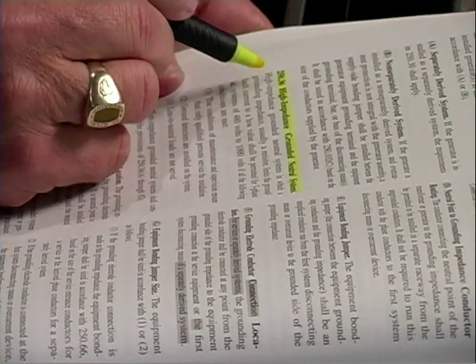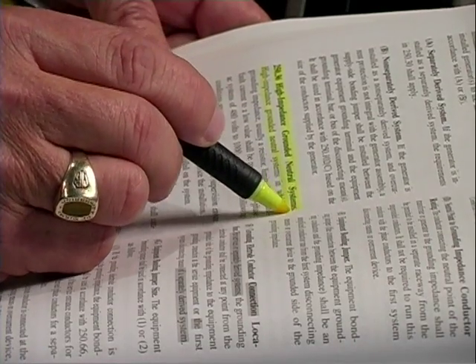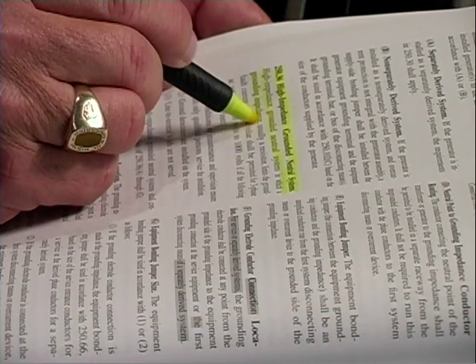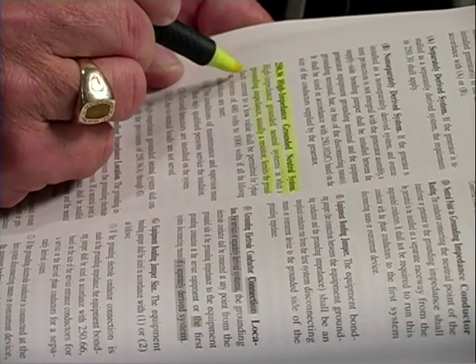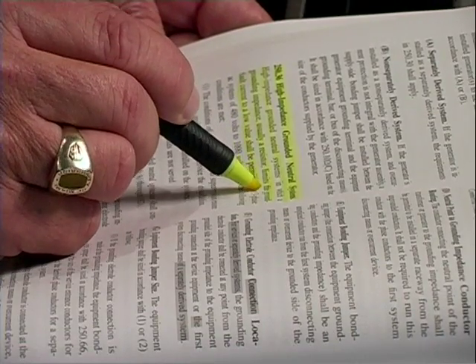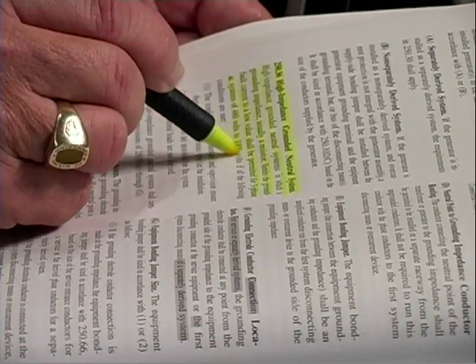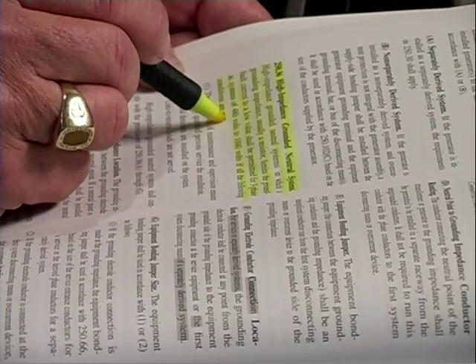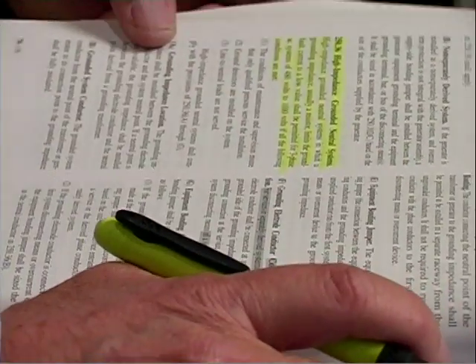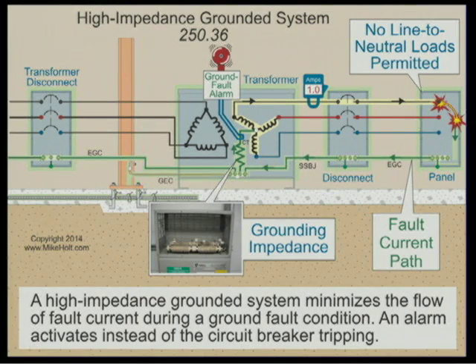High impedance, I'm going to read it. High impedance grounded neutral system is a system in which a grounding impedance, usually a resistor, limits the ground fault current to a low value for three-phase AC 480 volt systems if all of the following conditions are met. That means that this is a 480 volt system. So let's hold that concept there. This is 480 volts. Now, high impedance grounded systems are 480 volts.